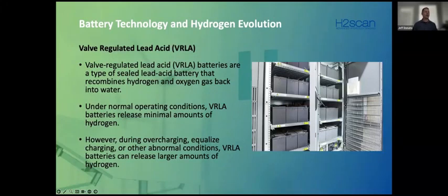We are seeing more valve regulated batteries in the utility space, which is interesting to see, with the emergence of what we call lead plante batteries, or pure lead batteries. We're seeing these a little more in various applications because of the cyclability, as well as the ride through properties of these batteries, which are showing a lot of promise when it comes to reliability. These are called sealed batteries in a lot of cases, and a lot of people call them maintenance free. In reality, they have a vent on top that is more of a pressure vent. In normal operation, the battery is recombinant.